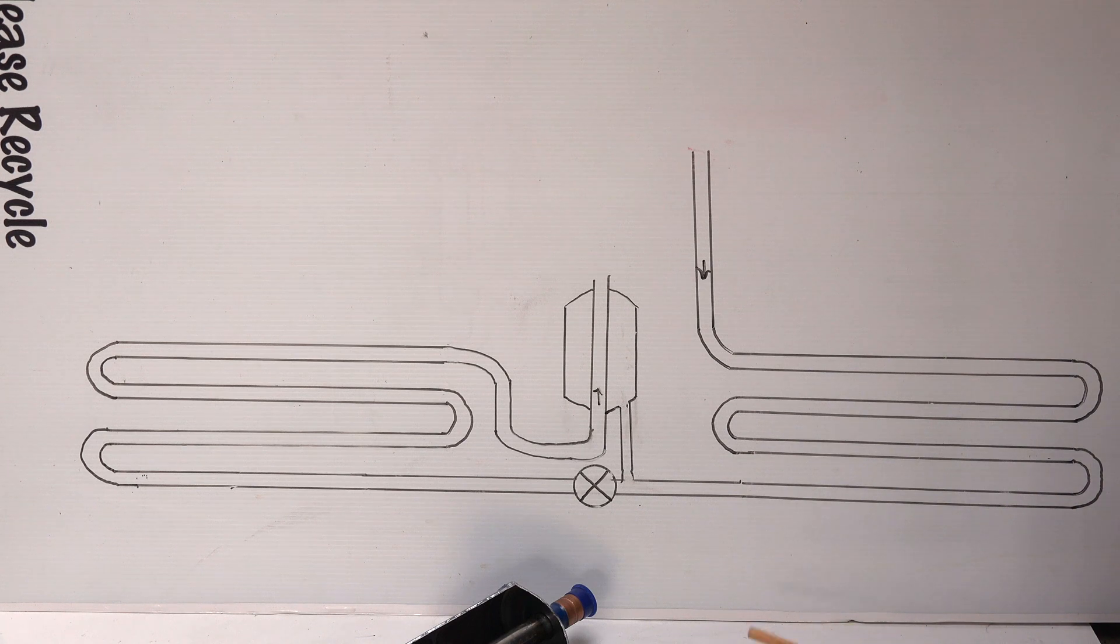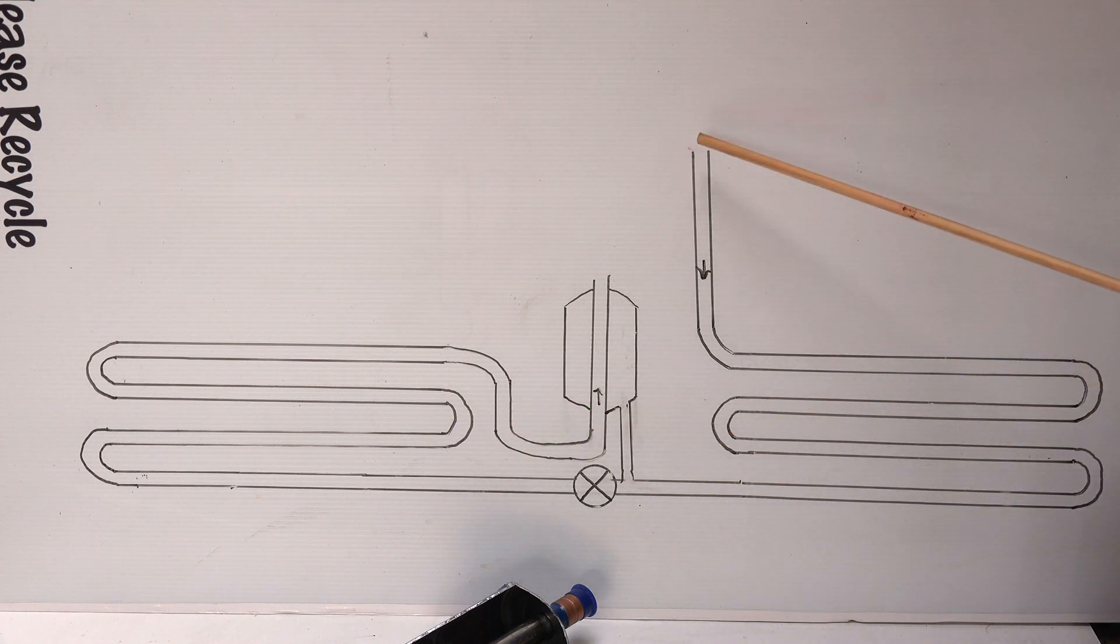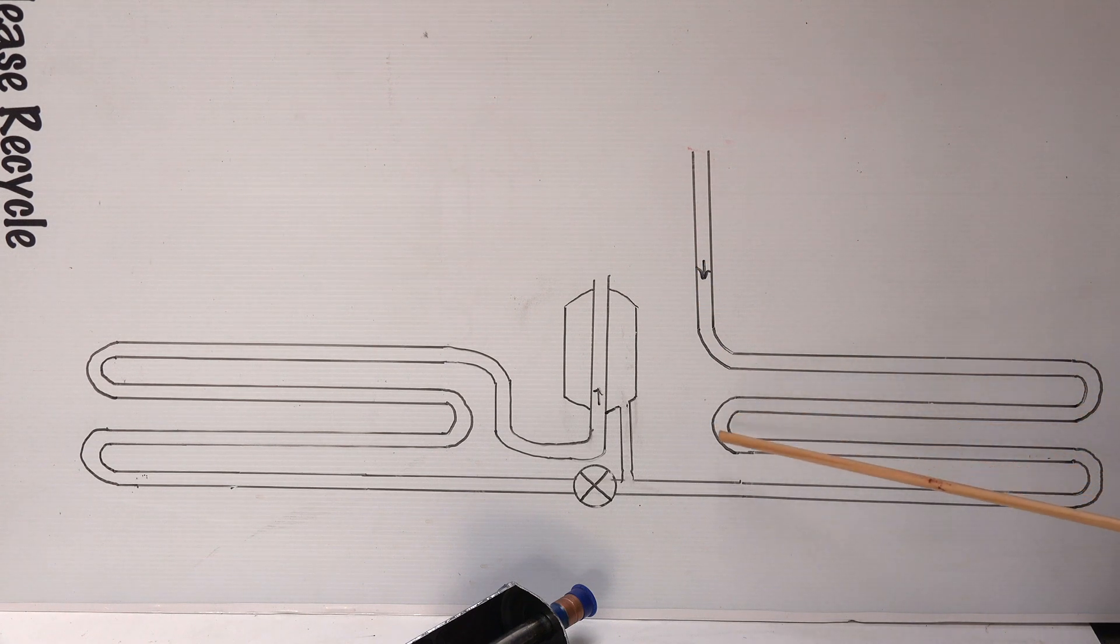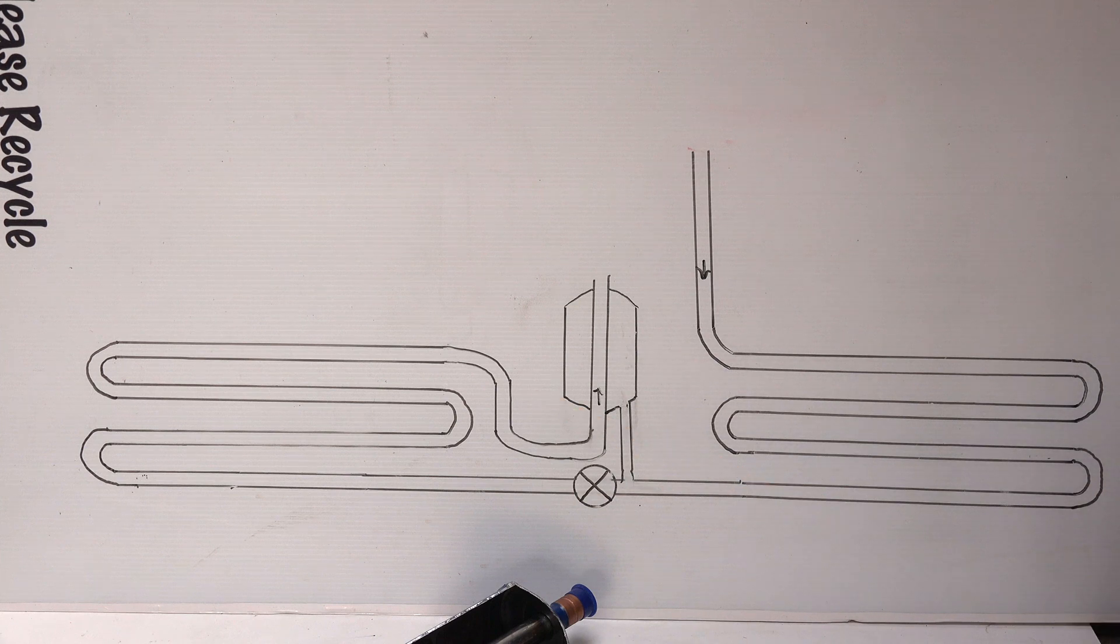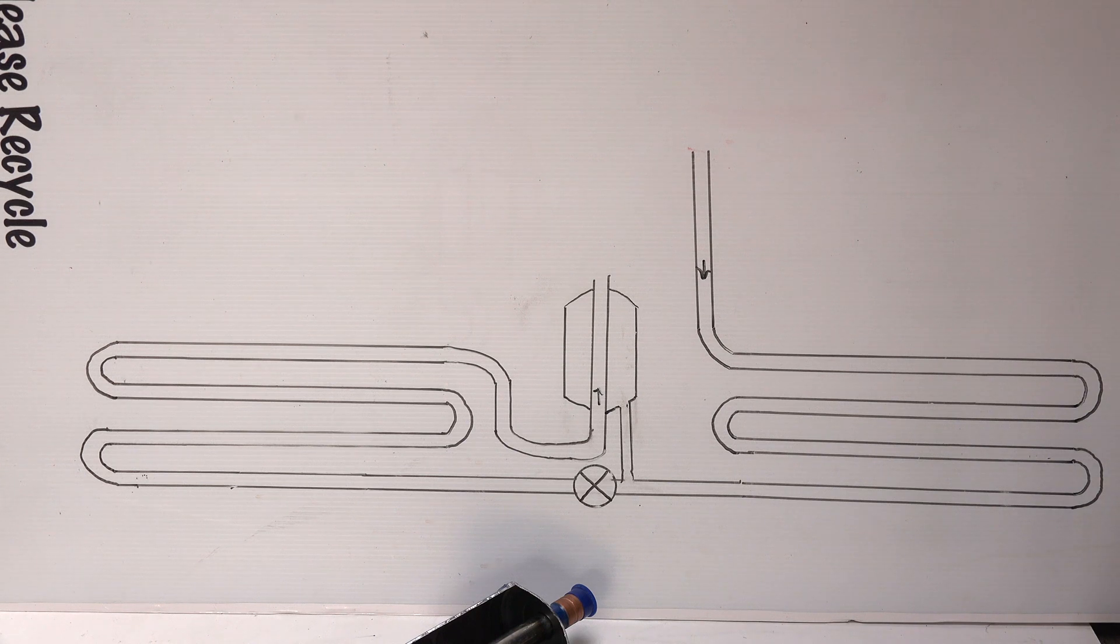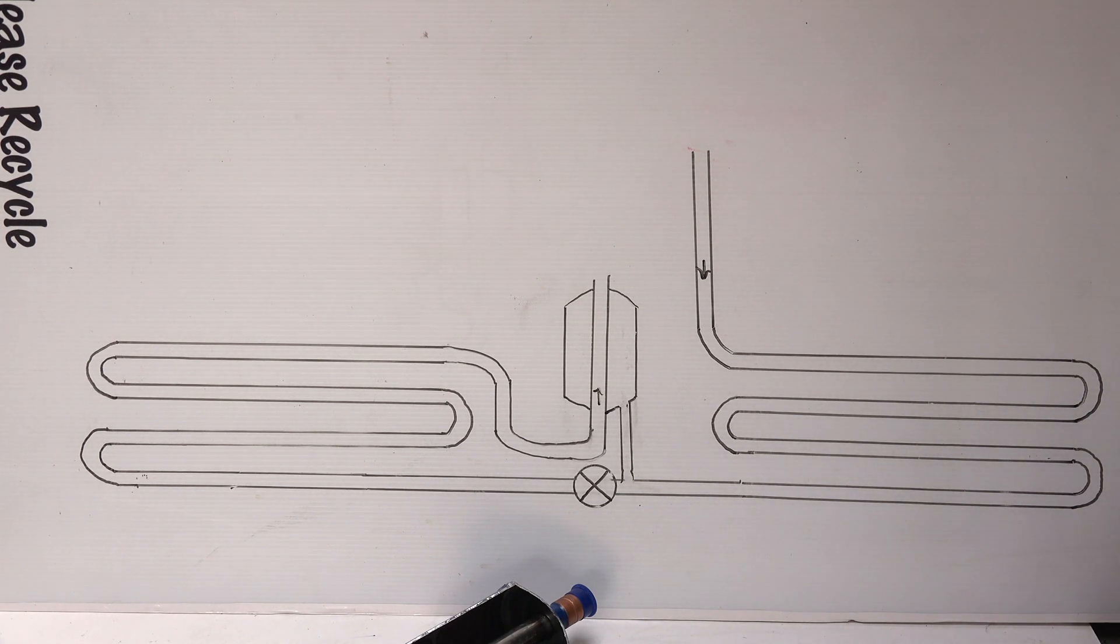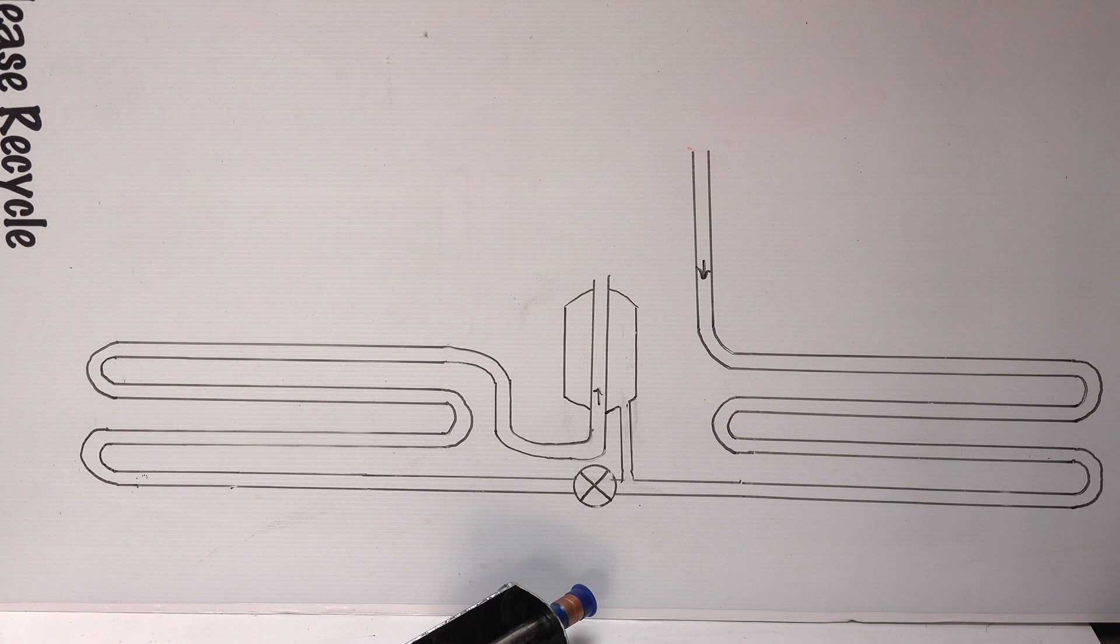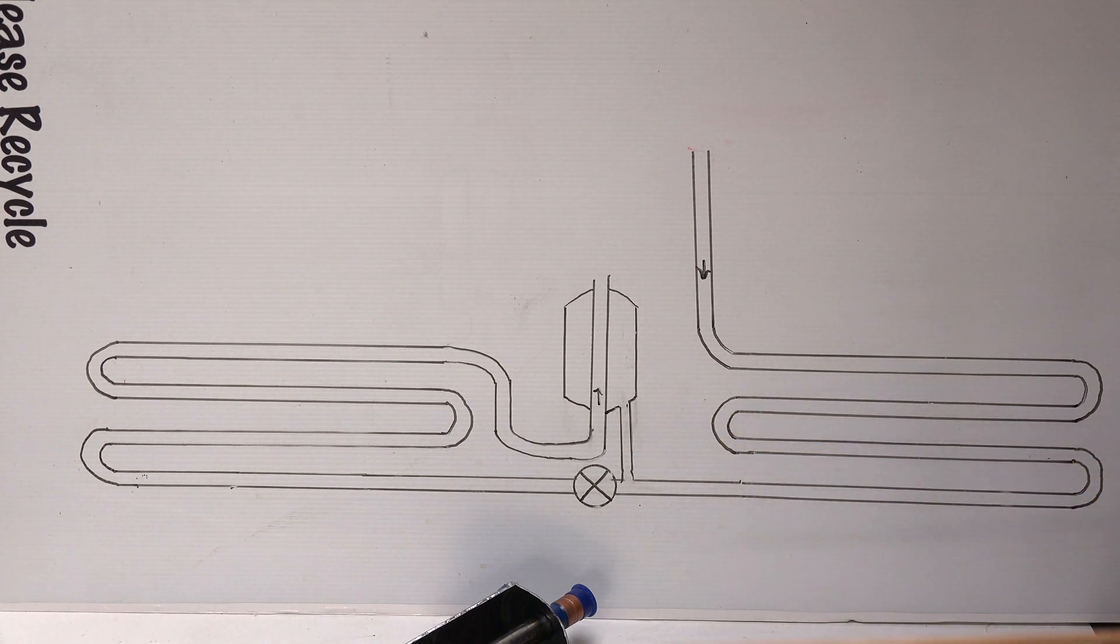So that refrigerant ends up going through the discharge line and backing up behind this TXV. Now I've seen this happen. I couldn't figure out what it was, but especially when you had mismatched indoor and outdoor units where I'd say have a Trane outdoor unit and a Carrier indoor unit, something like that.